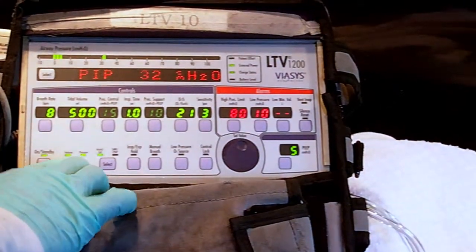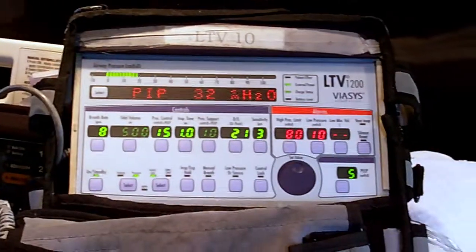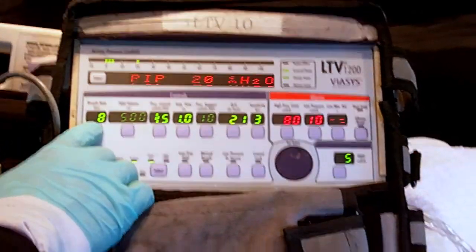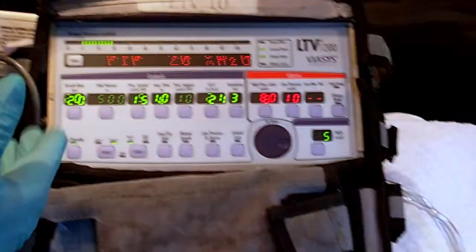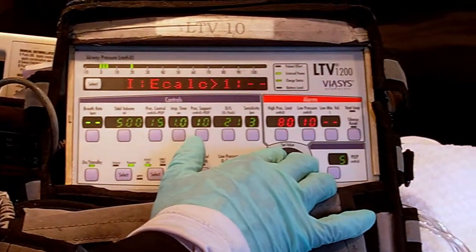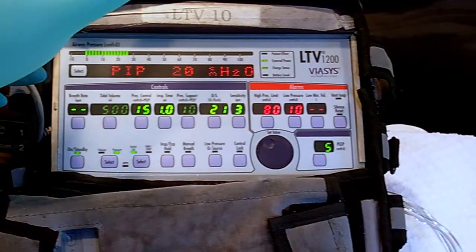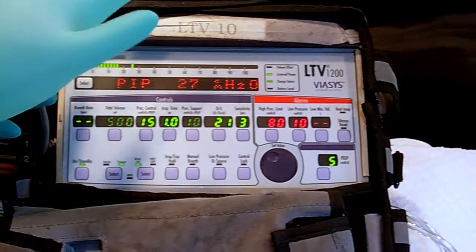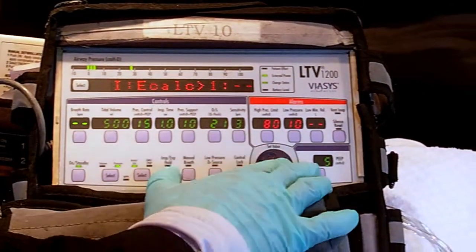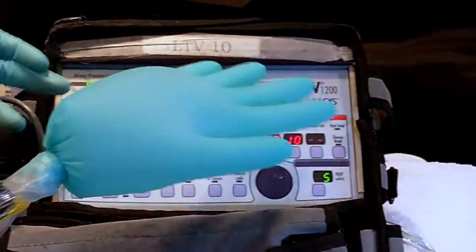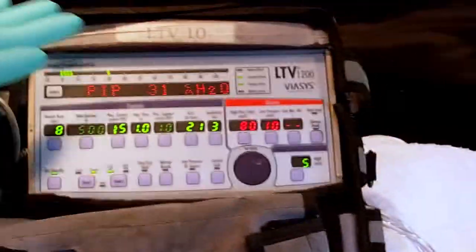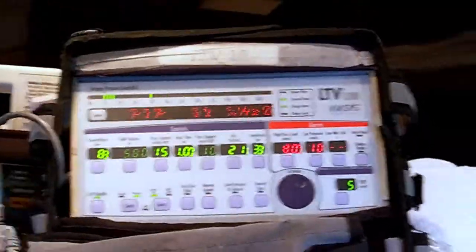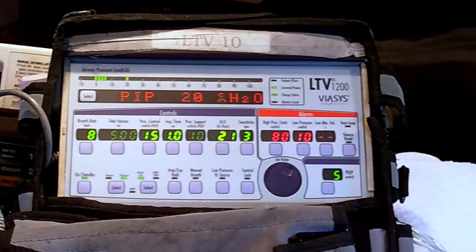Then we have pressure assist control. Again, same thing — it's a combination of pressure control breaths and pressure assist breaths. If we set the breath rate high, say 20, the machine will deliver controlled breaths at 20. If we set it at none, it's all going to be dependent on the patient to trigger the breaths. And if you put the breath rate somewhere in the middle, like eight, the machine delivers eight breaths a minute and the patient, if they want extra spontaneous breaths, triggers the ventilator on their own and gets the extra breath. That's why it's called pressure assist control.